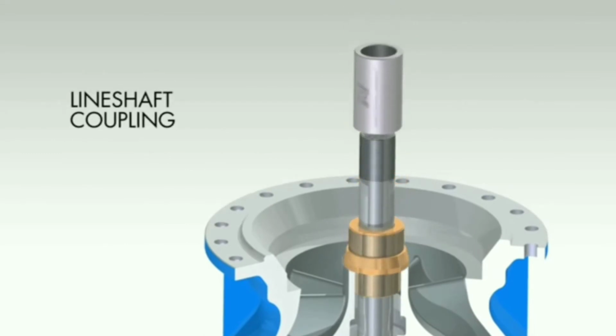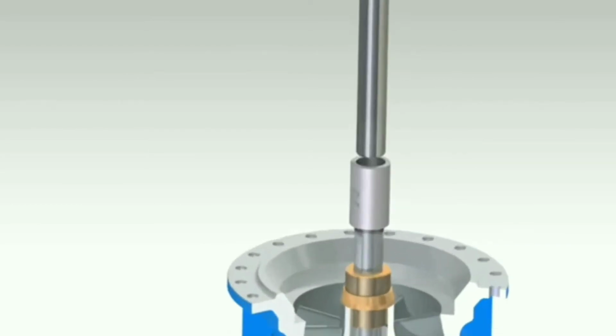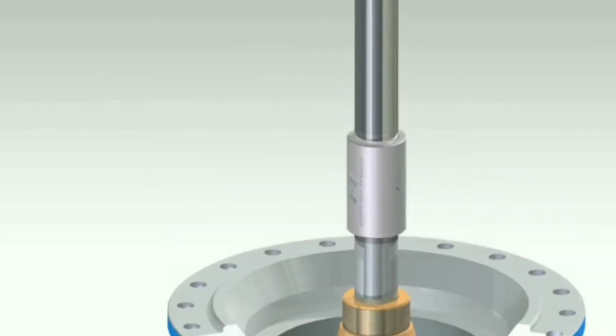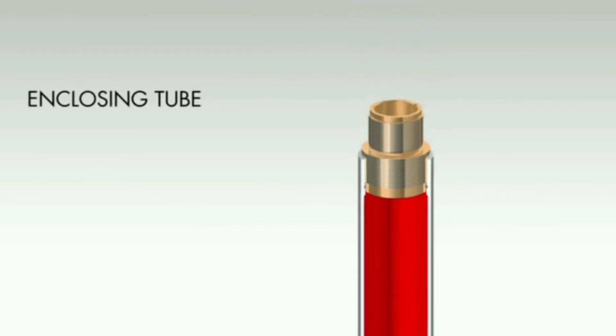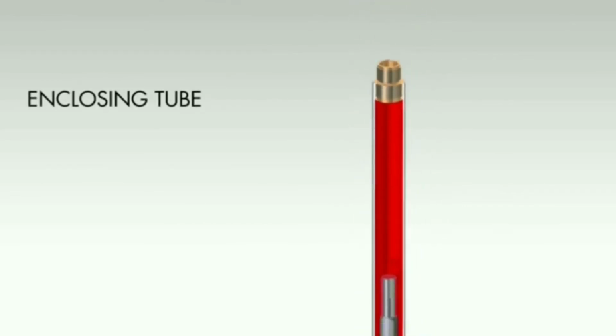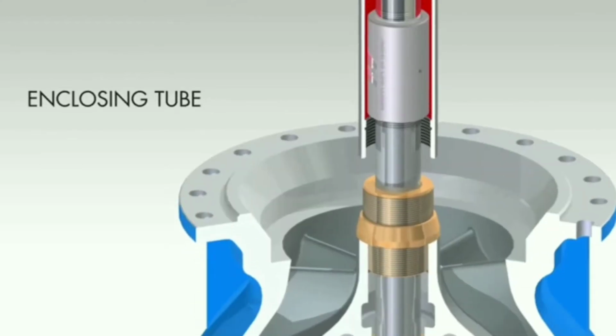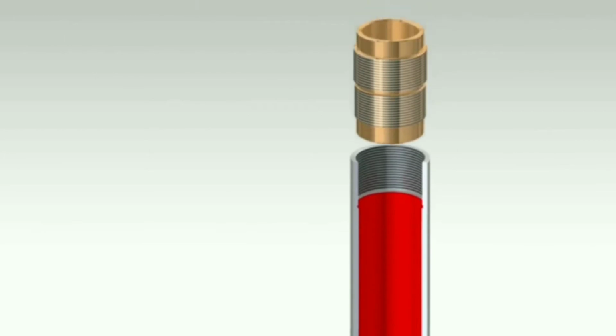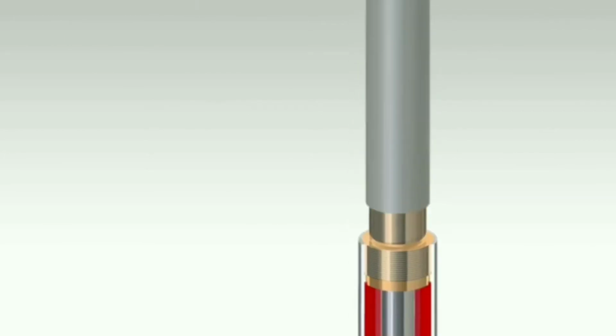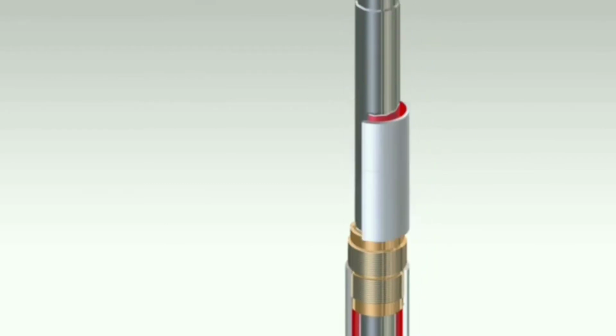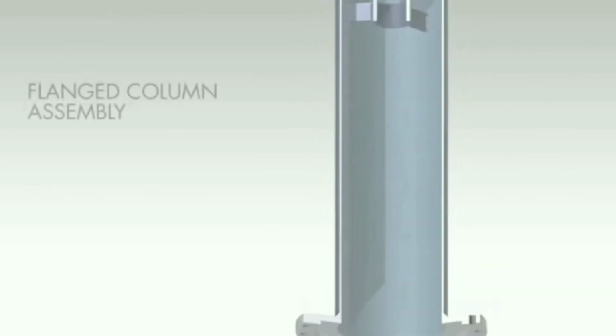Water enters the pump at the bottom through a bell-shaped part called the suction bell, and the vertical turbine pump starts to work. From there it is moved into the first stage impeller, which raises the water velocity. The water then enters the diffuser bowl immediately above the impeller, where the high velocity energy is converted into high pressure. The bowl directs fluid into the next impeller located immediately above it, and this process continues through all stages of the pump.